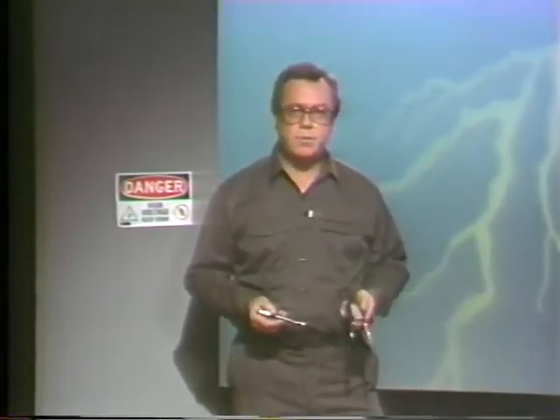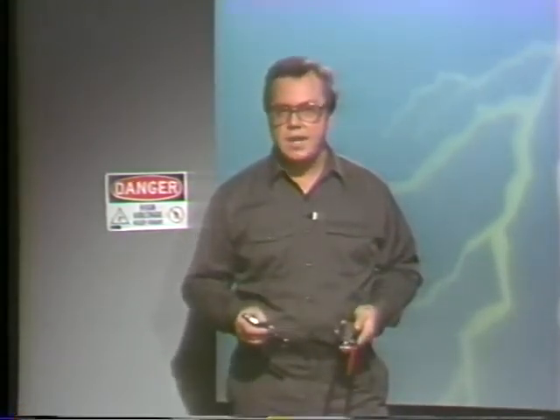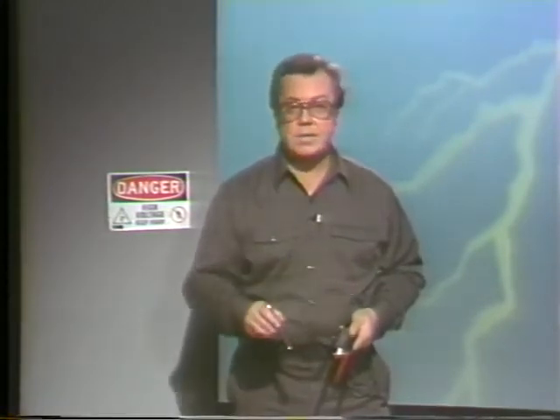The second important point is, how much do you trust these things? Well, you don't. Instead, you test the instrument before and after you check a circuit that's supposedly dead. You find something hot so you can make sure that your detector will register voltage. If there's nothing hot, you can check it on an approved test device. Then you check the de-energized circuit, and to make sure the device didn't die in between, you check it on a hot circuit again. That way, before you go sticking your hands into a bunch of wires, you can be pretty positive about what's hot and what isn't.